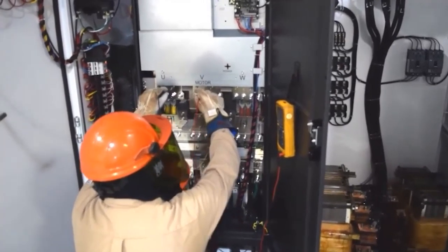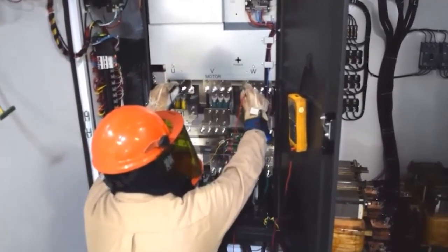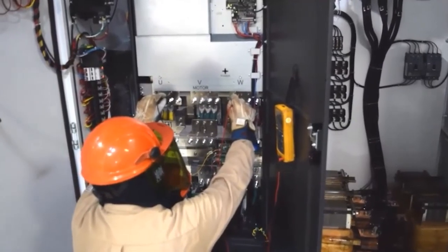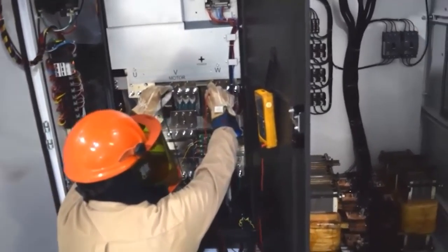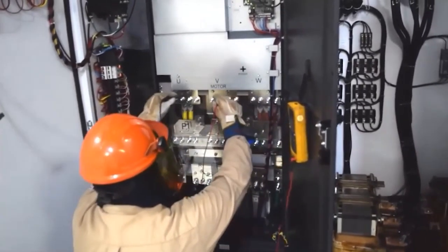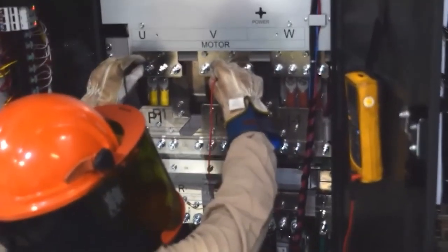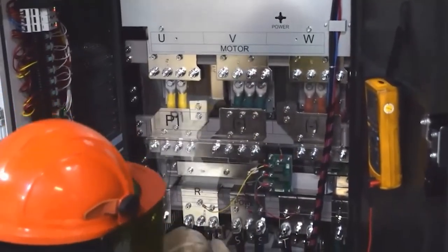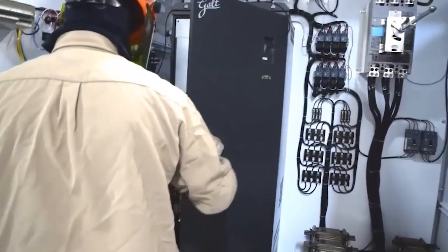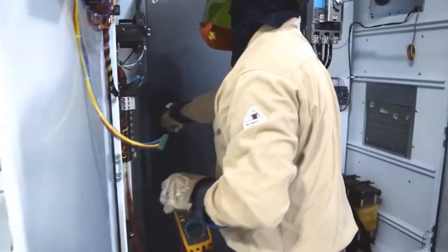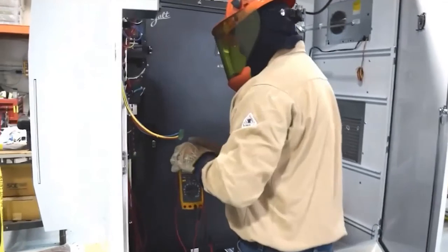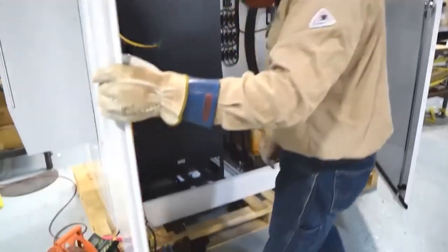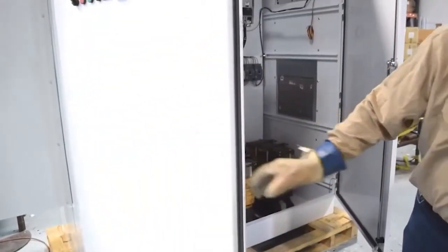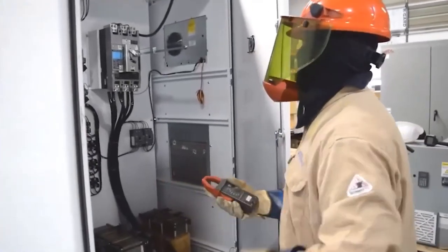Now, when you measure this voltage, it's normal to measure a little high with a multimeter. For instance, this VFD is putting out about 460 volts, and on my meter right now I'm measuring something around 515 volts. The reason my meter's picking it up that way is because of the PWM of the VFD. So don't be concerned if you're measuring something higher than what the keypad says, but what you do get concerned about is if your voltages from A to B, B to C are consistent. Once again, they need to be within about 1 volt of each other.